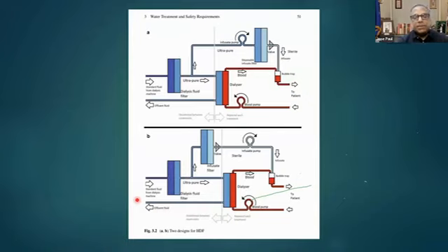The generation of the dialysis solution by the machine itself is known as online hemodiafiltration. There are two methods by which you can do this. The standard dialysis solution from the machine is taken to another filter. This filter is a good bacteria filter, and it also functions as an endotoxin filter.